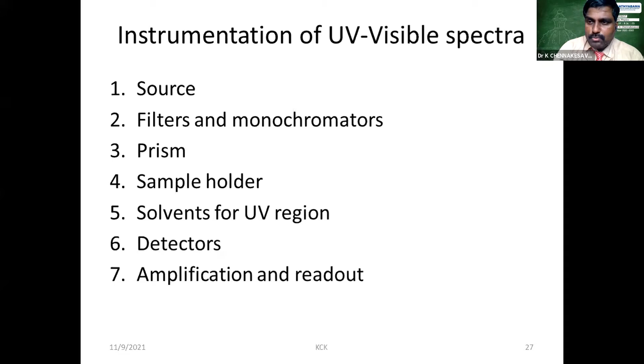Okay, the source for UV visible radiation is the tungsten lamp we use. We are still using the tungsten lamp in our rural areas. The wavelength of the tungsten lamp will be from 350 to 800 nanometers. And if you come to the hydrogen or deuterium lamp, the wavelength will be from 160 to 350 nanometers, and xenon lamp 200 to 1000 nanometers.